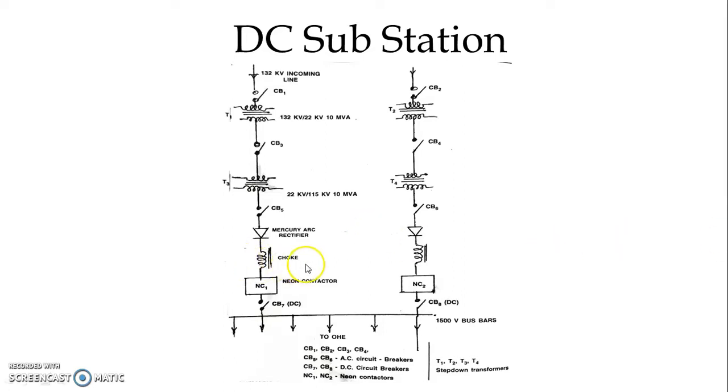We require smoothing equipment because the output is not pure DC, so we require to smooth out the output of the rectifier. We have various protection and metering devices, and we have circuit breakers to isolate the circuits, on the AC side as well as on the DC side. The DC power is now supplied to the 1500 volt bus bar, and through the bus bar and through the feeder it is transmitted to the overhead catenary at various distances.